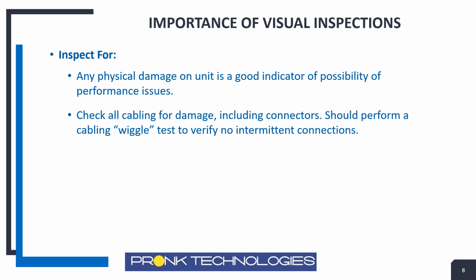The cabling. Cabling is a common issue that can come up in failures. It's important that we always check the cabling, be it the ECG cable, SPO2, the multifunction or the quick combo cable as they refer to it for the defib pads. All of these things should be thoroughly checked, including the connectors on the accessories, connectors on the medical devices. Anything that can cause an intermittent connection can be really problematic because in one moment it could work and maybe the next moment when someone is moving cabling around, the unit around, it may stop functioning as you would expect. So I always like to emphasize that it's important that we do a wiggle test or the cable wiggle test, making sure you're trying to verify that under no circumstances do you lose communication, do you lose the performance of that particular cable, regardless of how you orient the cable. And so can't emphasize enough the importance of doing the cable testing, particularly on defibrillators.